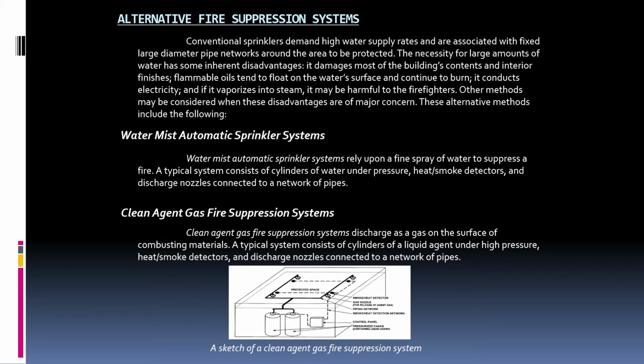Alternative fire suppression systems. Conventional sprinklers demand high water supply rates and are associated with fixed large diameter pipe networks around the area to be protected. The necessity for large amounts of water has some inherent disadvantages. It damages most of the building's contents and interior finishes. Flammable oils tend to float on the water surface and continue to burn. It conducts electricity, and if it vaporizes into steam, it may be harmful to the firefighters. Other methods may be considered when these disadvantages are of major concern. These alternative methods include the following.